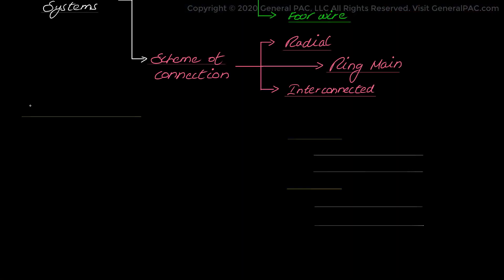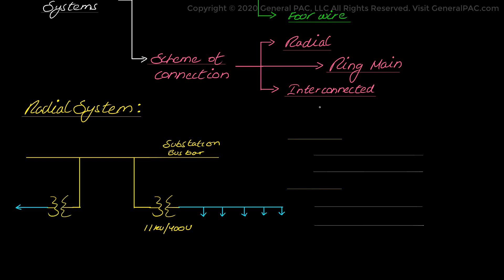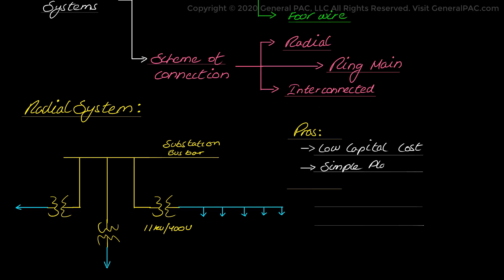Continuing on to distribution systems. First, we have radial systems. In this type of system, separate feeders radiate from the substation and feed the distributor, branching into sub-feeders and laterals which extend to all parts of the area being served. A radial system is used when the load is operating on low voltage and the substation is located at the center of the area covered by the load. It has a low initial capital cost, requires simple planning, and is the simplest among all.